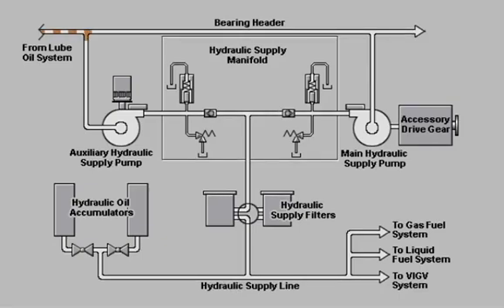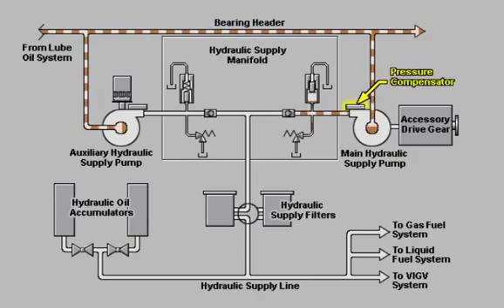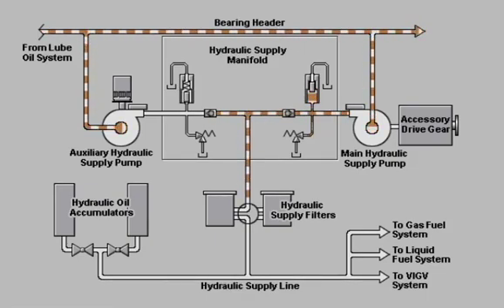When the gas turbine is operating at 100% speed, the main hydraulic supply pump takes lube oil from the bearing header and delivers it to the hydraulic supply manifold under very high pressure. The pressure compensator in the main hydraulic oil supply pump regulates the output pressure of the pump. The output from the hydraulic supply manifold is filtered in the active hydraulic supply filter.